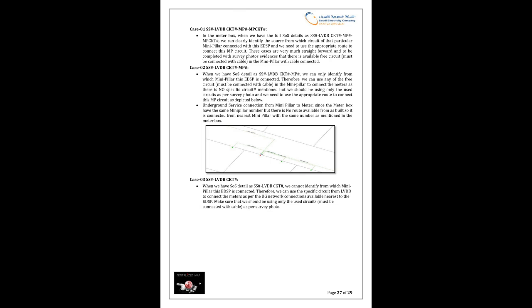Case 3: SS, LVDB, CKT. When we have SOS detail as SS, LVDB, CKT, we cannot identify from which mini pillar this EDSP is connected. Therefore, we can use the specific circuit from LVDB to connect the meters as per the UG network connections available nearest to the EDSP. Make sure that we use only the used circuits, which must be connected with cable as per the survey photo.